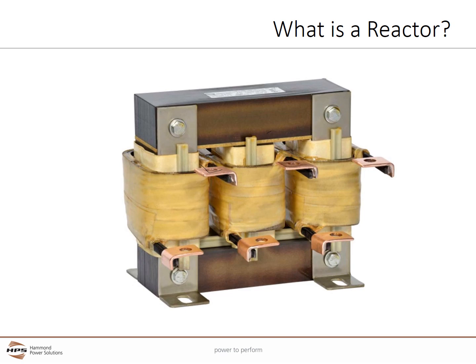This is a typical three-phase iron core line reactor. It has 3 coils and an iron core. Unlike a transformer, which has a primary and secondary coil for each phase, a line reactor has just one coil and does not provide isolation or the ability to change voltages through winding ratios.